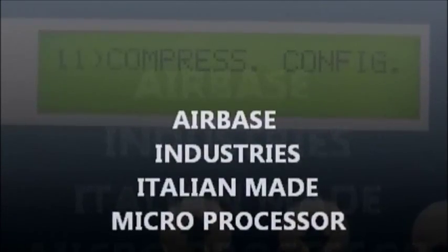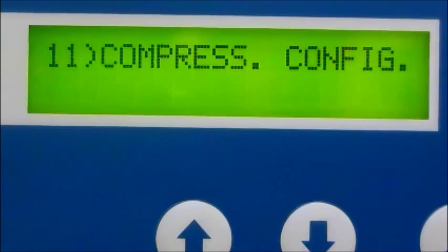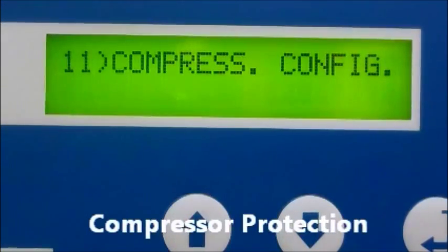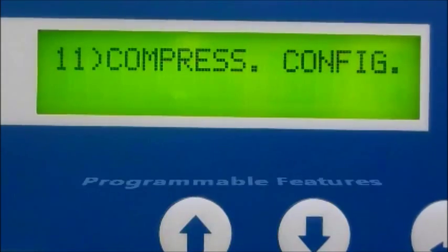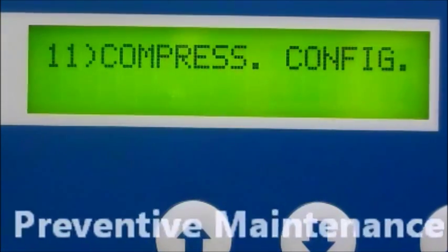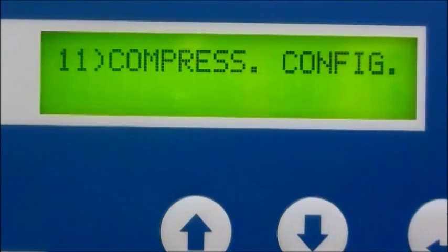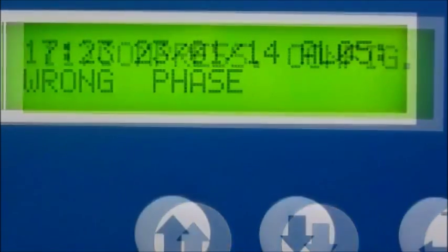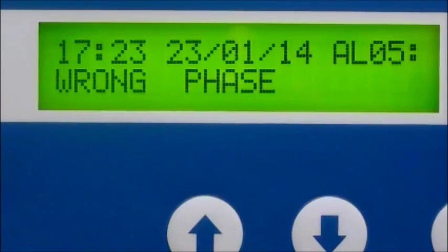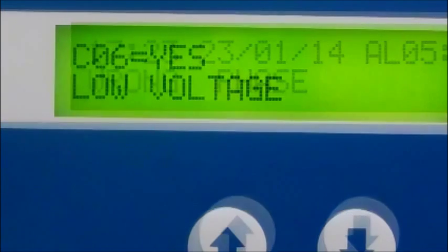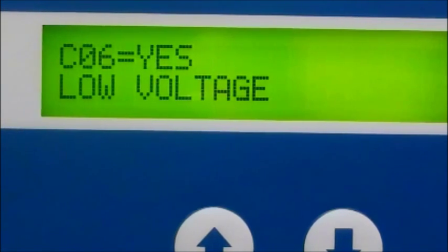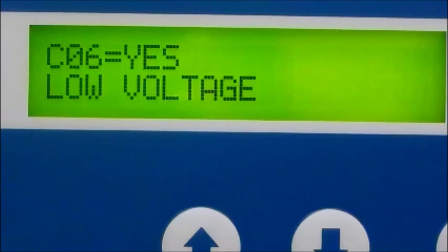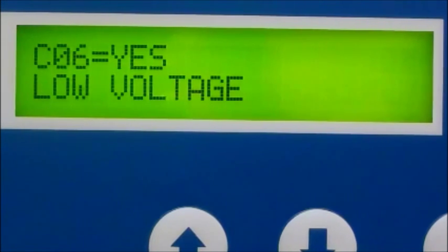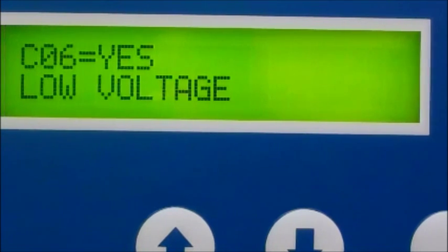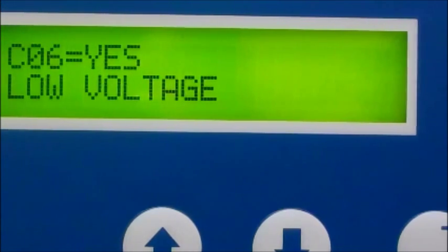The Airbase Industries microprocessor is the brains of the operation. Let's quickly touch base on 4 key features of the PLC: compressor protection, compatibility, programmable features, and preventive maintenance. Okay, let's break this down into further detail. We can start with compressor protection features. The PLC senses pump reverse rotation and has loss of phase detection. And also high-low voltage protection, high and low temperature sensing, low oil detection and shutdown, and control of maximum motor starts per hour, coupled with motor over amp shutdown.